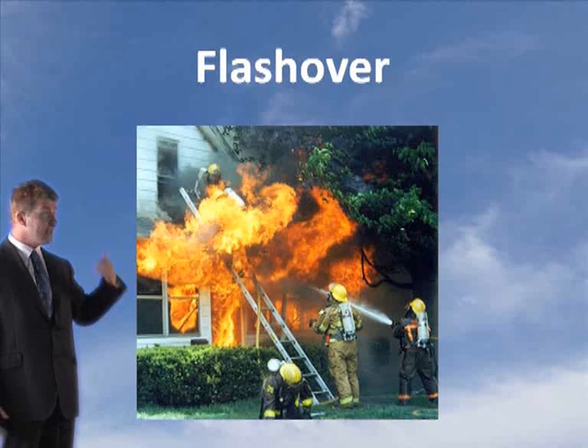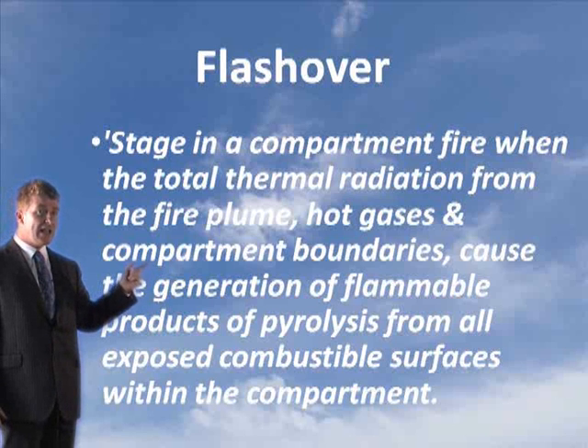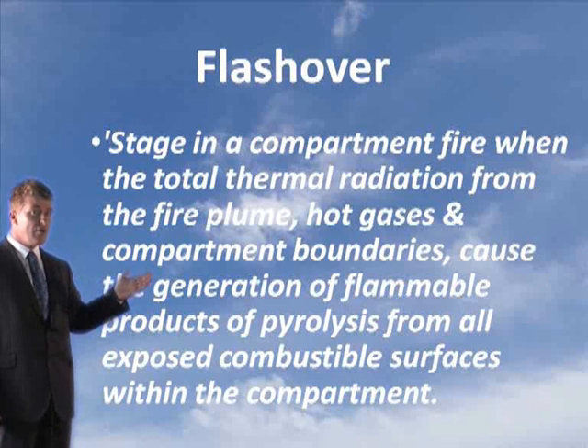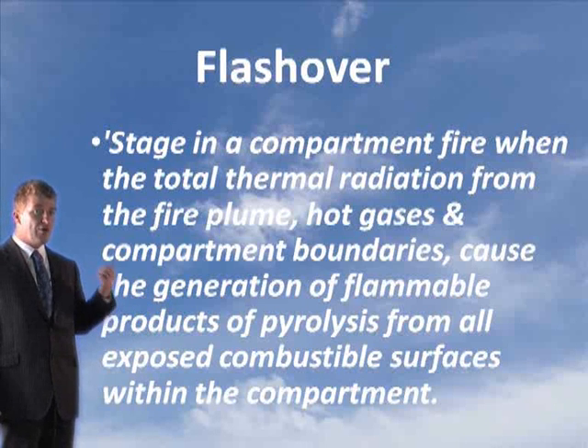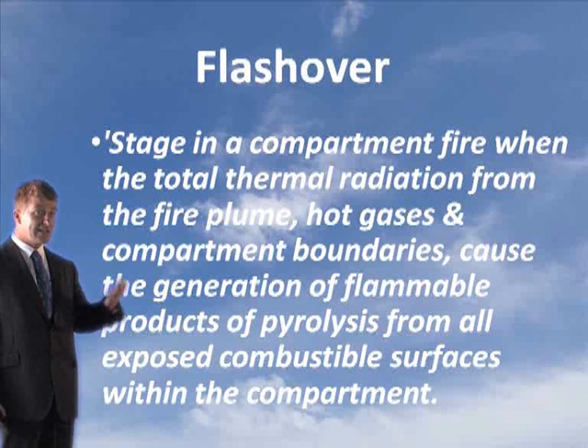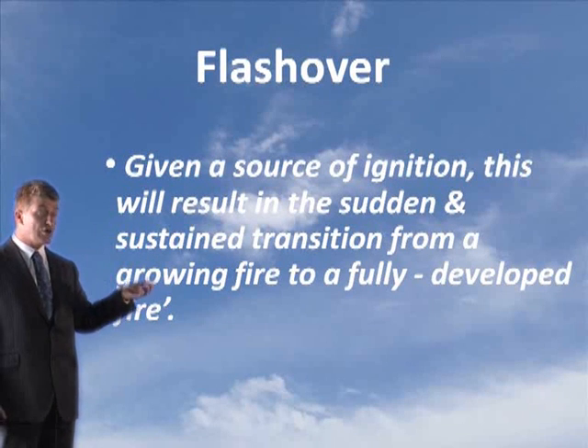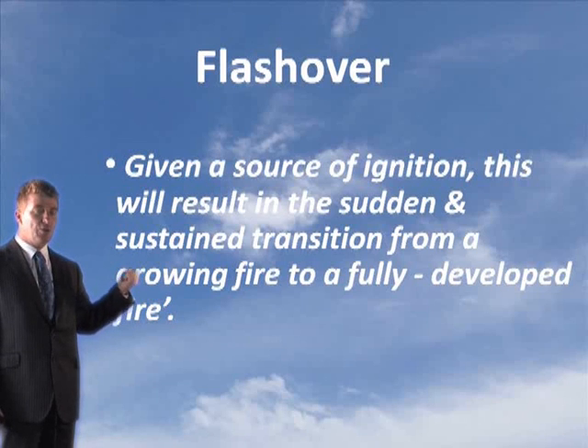The definition of flashover is a stage in a compartment fire when the total thermal radiation from the fire plume, the hot gases and the boundaries cause the generation of flow of the products — everything's heating up and giving off gases, pyrolyzing from all exposed combustible materials within the compartment. Given a source of ignition, or if it reaches its auto ignition temperature, this will result in the sudden and sustained transition from a growing fire to fully developed. In other words, following flashover, you've got a fully developed fire.